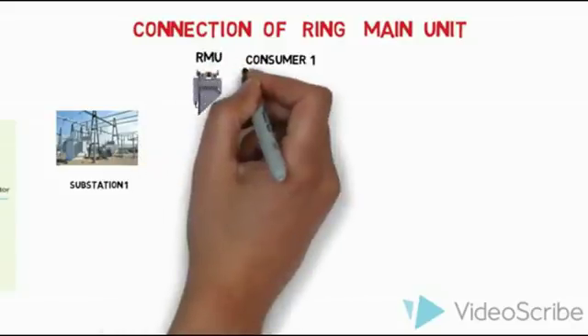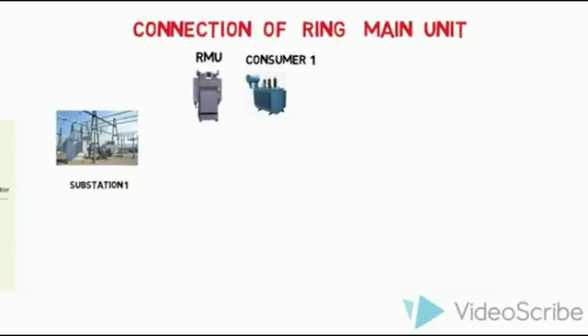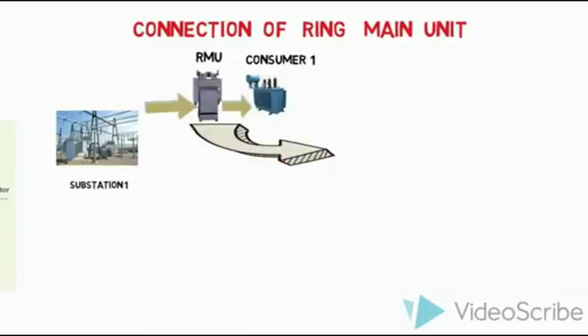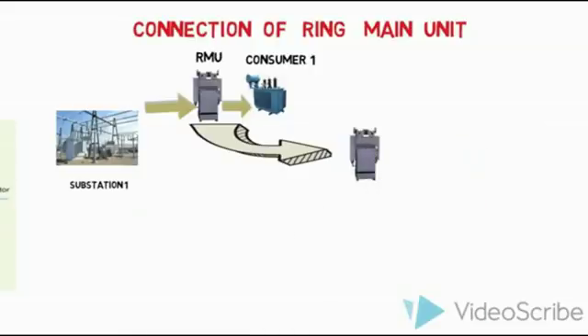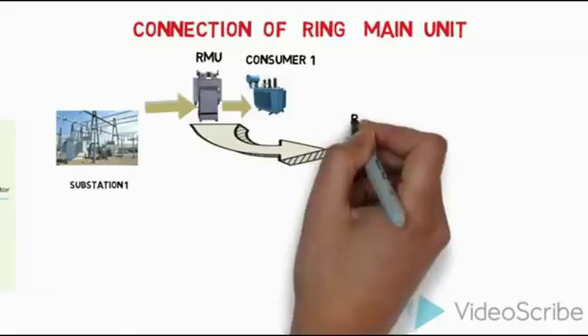We need to put a ring main unit here. The supply from the substation first reaches the ring main unit, then the ring main unit connects to a transformer, and the transformer gives supply to the consumer. After that, the ring main unit has a loop — a T-connection — and that T-connection ring main unit sends supply to another ring main unit. That next ring main unit connects to the next transformer for the next customer.